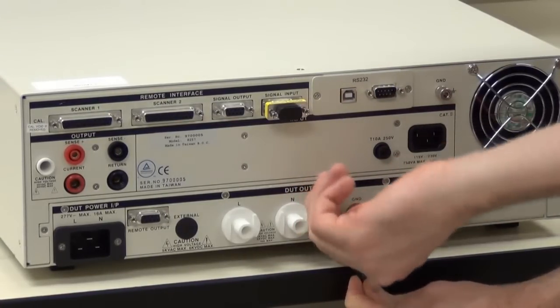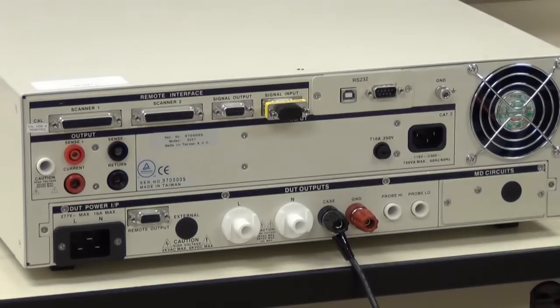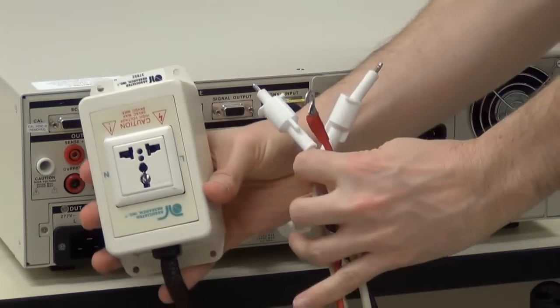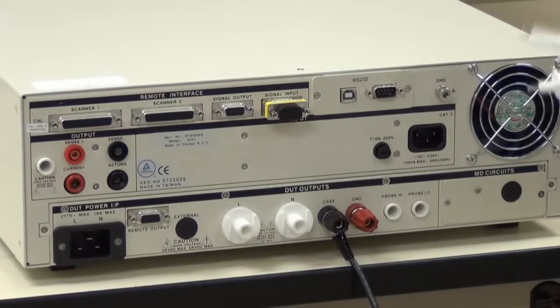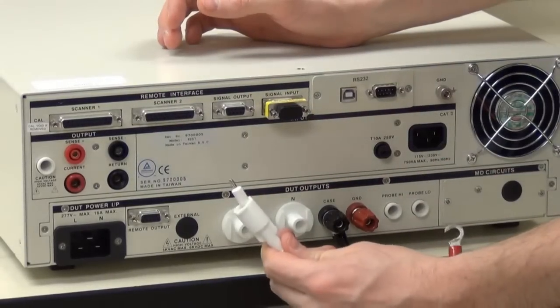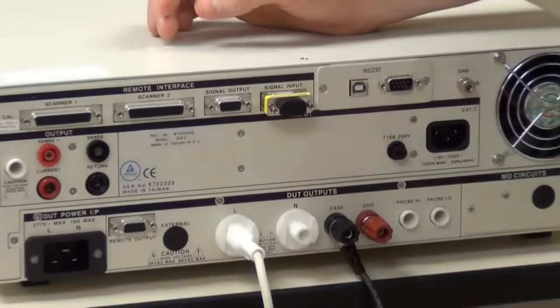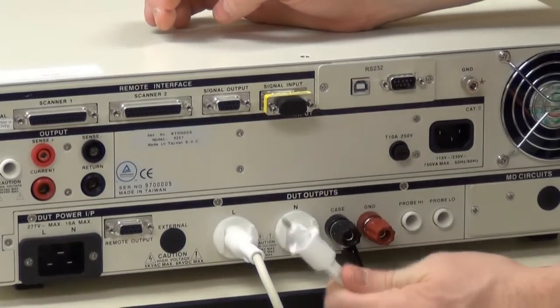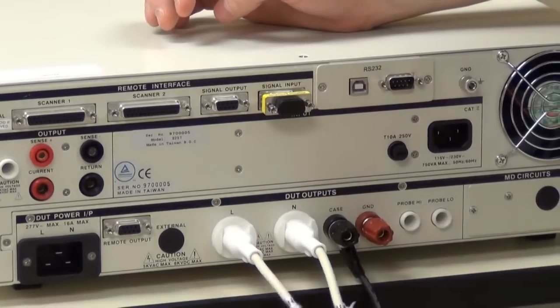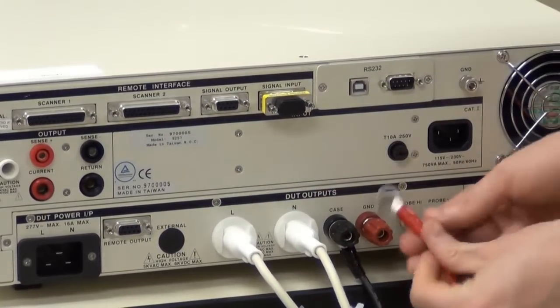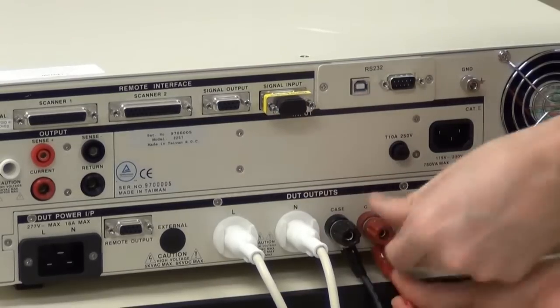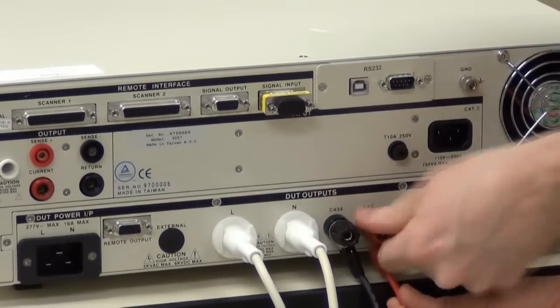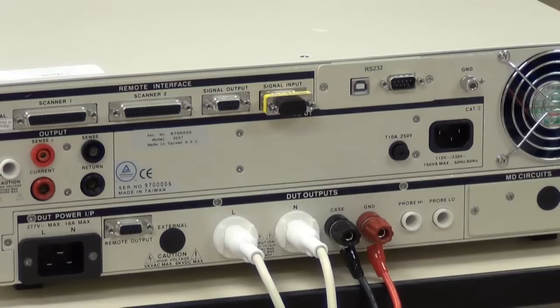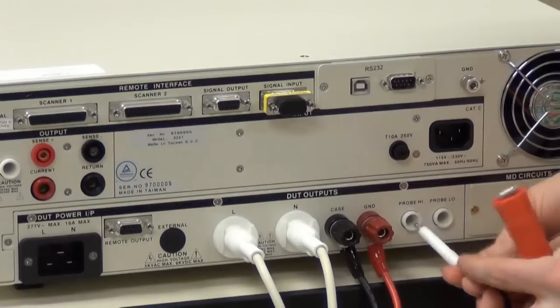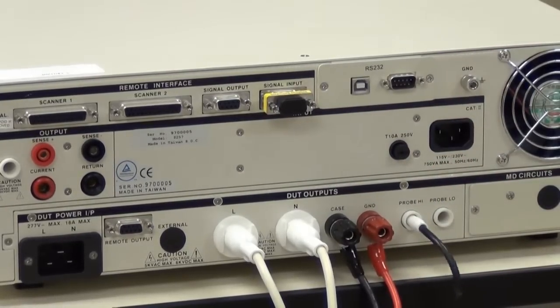Next, using the adapter box, connect the line lead from the adapter box into the L terminal and the neutral lead into the N terminal. These two types of terminals are twist lock, so simply push in and turn to the right to lock into place. Next, take the ground terminal, use the hook lug to put onto the ground post, and turn to the right to lock shut. Finally, if you're making patient or enclosure leakage measurements for a line leakage test, use the probe high and probe low terminals by plugging in 2 high voltage leads.